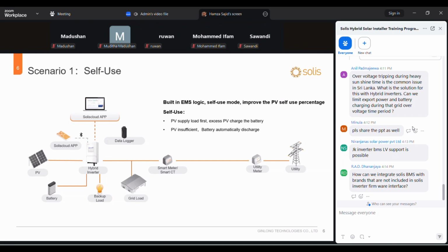Okay. As I told earlier, if any situation like this where the batteries cannot be communicated with the inverter, you can send us the battery, or we can send you the test. So you can check the compatibility of the BMS with the inverter. If it passed, we can give a firmware upgrade for the inverters, which can help you communicate with the battery. But let's suppose the battery is not compatible by the communication system, then you also have options available with lithium ion 48 volt or 51.2 volt.